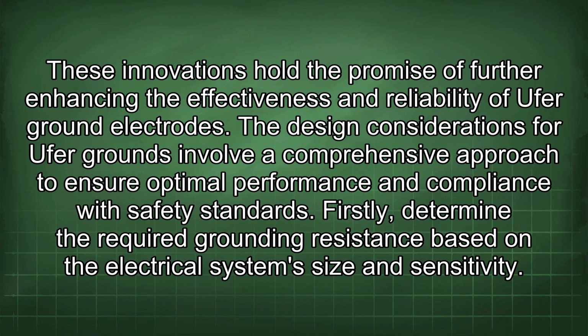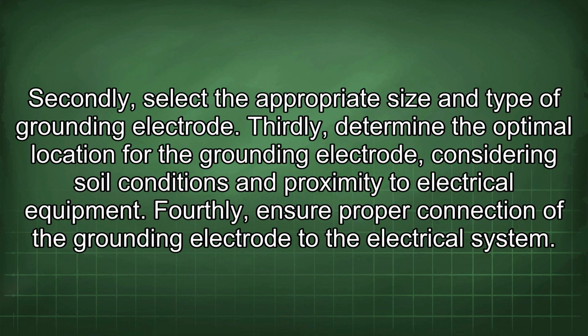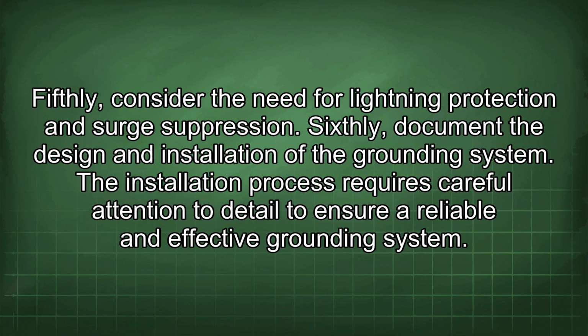Firstly, determine the required grounding resistance based on the electrical system's size and sensitivity. Secondly, select the appropriate size and type of grounding electrode. Thirdly, determine the optimal location for the grounding electrode, considering soil conditions and proximity to electrical equipment. Fourthly, ensure proper connection of the grounding electrode to the electrical system. Fifthly, consider the need for lightning protection and surge suppression. Sixthly, document the design and installation of the grounding system.